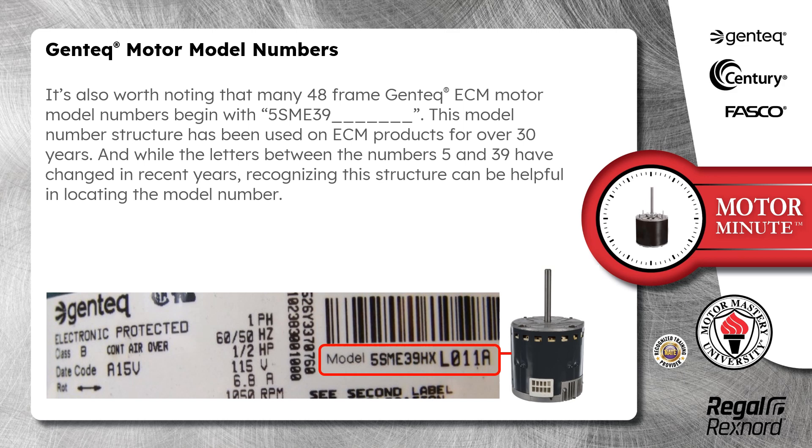It's also worth noting that many 48-frame Genteq ECM motor model numbers begin with 5SME39HX. This model number structure has been used on ECM products for over 30 years, and while the letters between the numbers 5 and 39HX have changed in recent years, recognizing this structure can be helpful in locating the model number.